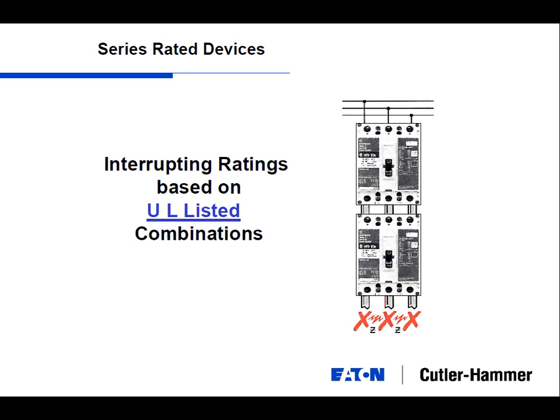You have to completely understand that if you go with a series rated system in this application of this building, I cannot tell you which is going to trip, my branch or my main. For $5,000 in your pocket, where would you have it? Just in a general warehouse? A general warehouse, yep.